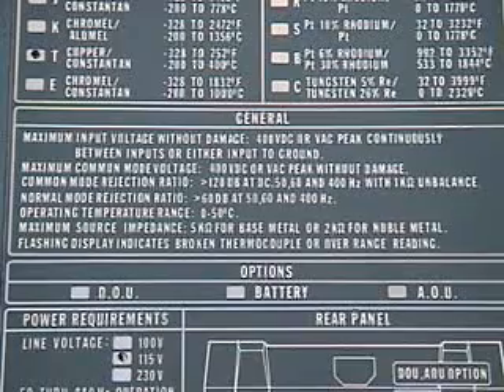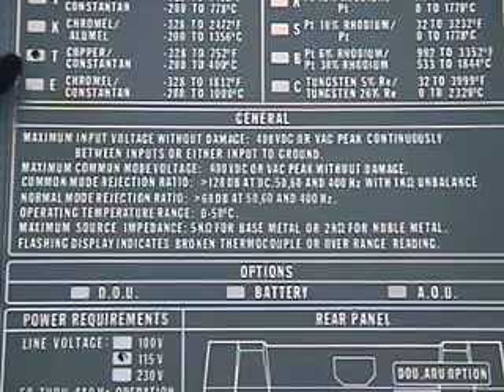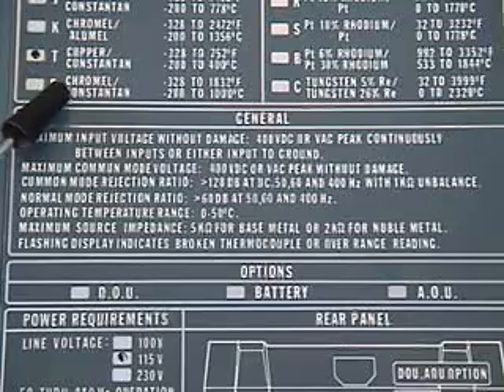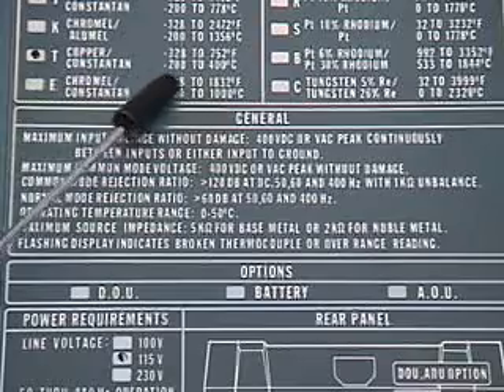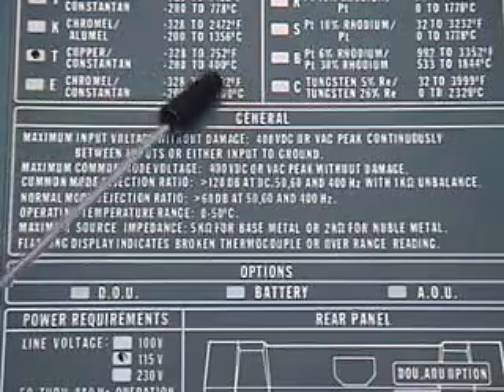The back of the device includes a label that reports various specifications for the instrument. It's shown to be configured for a T-type thermocouple, which is copper Constantan. This type of thermocouple can withstand a temperature range from negative 200 degrees Celsius to 400 degrees Celsius.